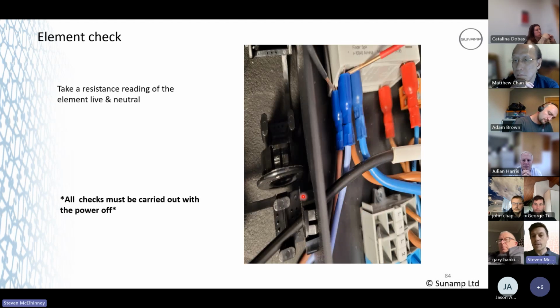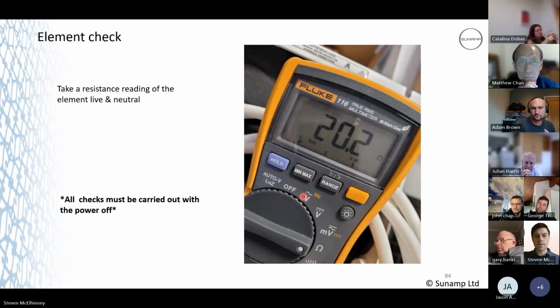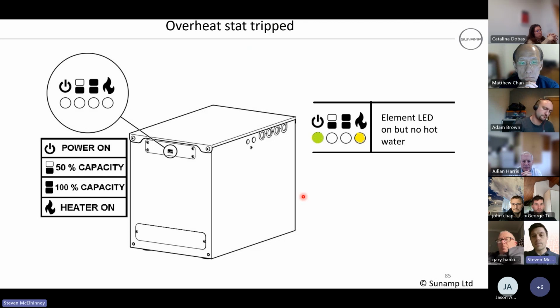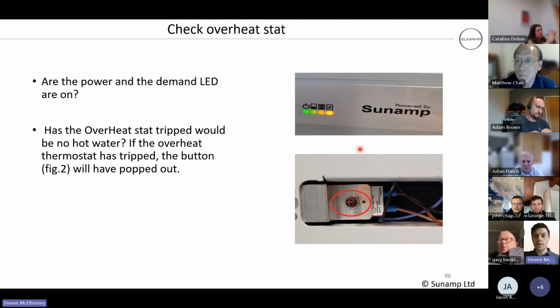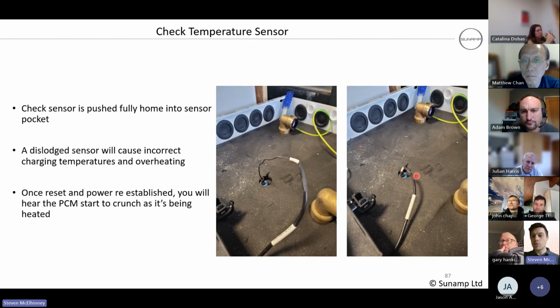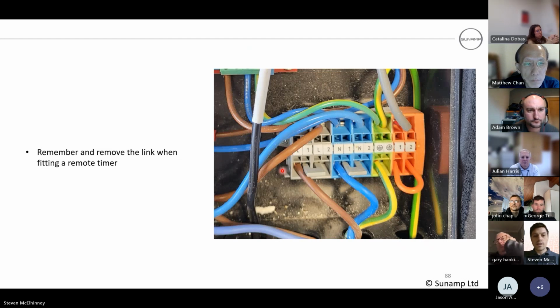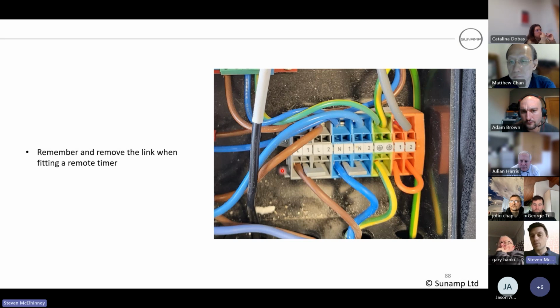That's just checking from the top at the relay, so that's checking the wires from the top down to the element and back again. Overheat stat tripping, this is the fault scenario you'll have. You have a power LED and element LED on, but no hot water. So it'd be a case of check your overheat stat. Has it popped? Press it back in. The next thing to do is make sure your temperature sensors are pushed fully home. If it's pulled out any, it's just going to overheat. I mean, that's a bit extravagant, but I have seen them completely removed before. Remember, remove the link if you're fitting a remote timer. Otherwise, the link will take priority over any timing cycle.